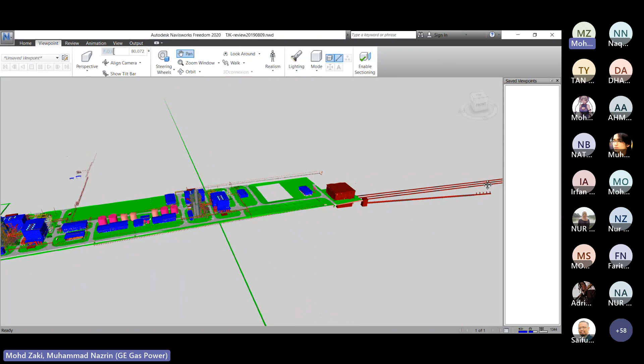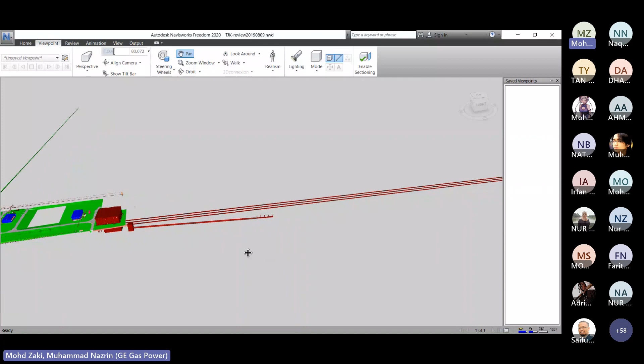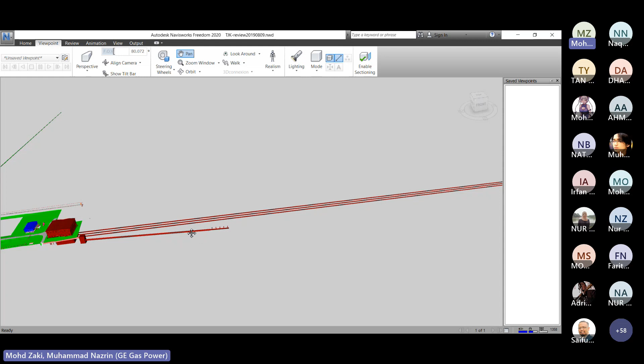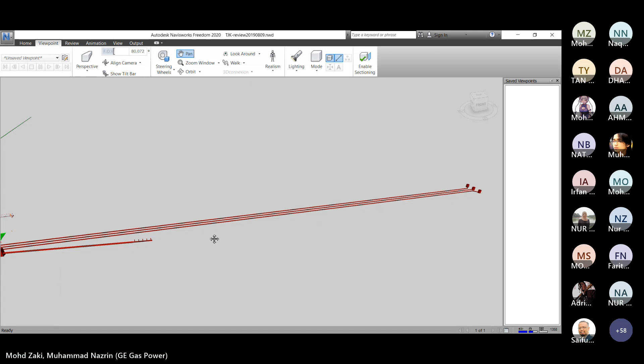Let's zoom out - this long pipe is the cooling water line. The cooling water pipeline is quite long, almost 2 kilometers. We take seawater from the sea. Why do we take such a long distance for the pipeline? Because if we take a short distance, say only 100 meters, the depth near the plant would be too shallow, so we don't want any slush or impurities going inside the cooling pipe. That's why we take seawater far away from the plant.